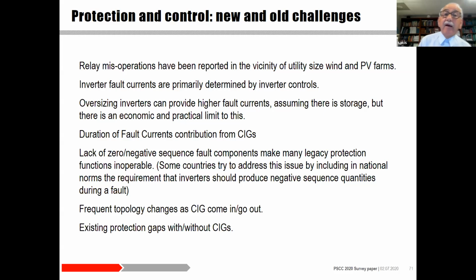Now, for a long time, people have been warning that inverter interfaced generation will generate misoperations in relays. And now we live in an era where we have seen these misoperations in actual systems for many years. As a matter of fact, Mario showed one particular case from the blackouts in California a few years ago. So what causes that? Well, inverter fault currents are primarily determined by the inverter controls. And in protection, we need high fault currents to detect faults. One approach there is to oversize the inverters, but of course that will have economic and practical limits.